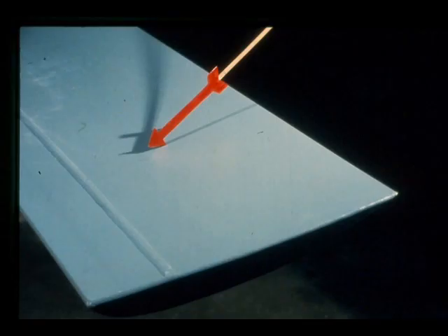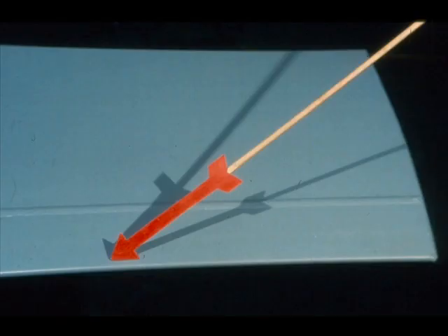Let's use this fan as an example. As you can see, the flat side of the blades are on the top. Therefore, this is the outlet or downwind side. Viewing the fan from the top, we next locate the leading edge of the blade, being pointed out by the workman. This means that the fan blades turn in this direction, which is clockwise. That's all there is to determining the direction of rotation.